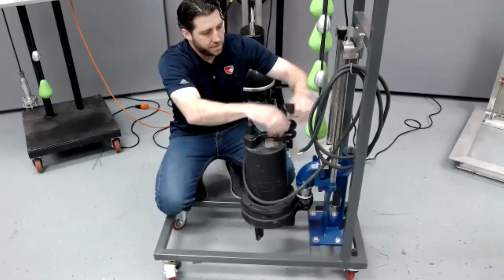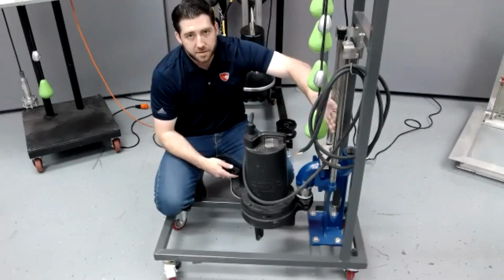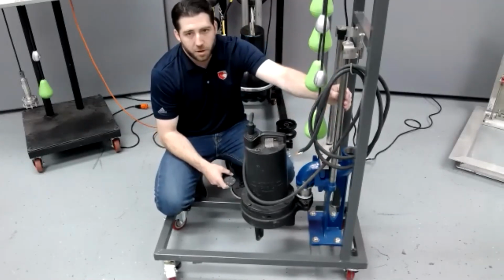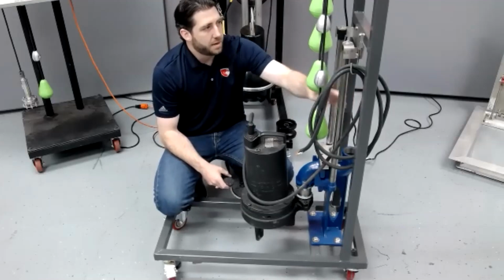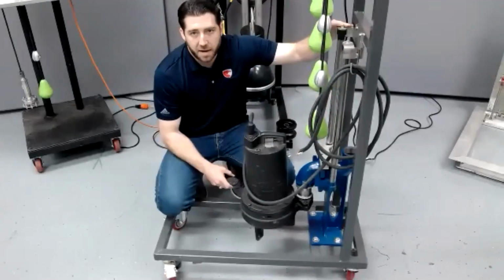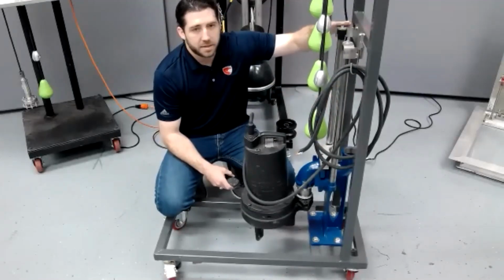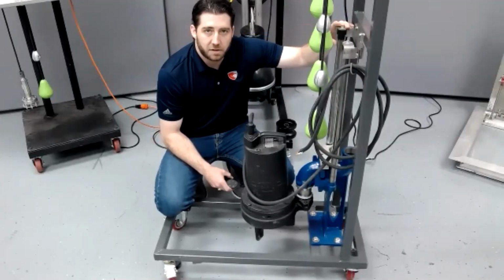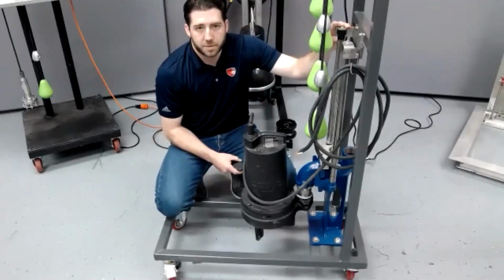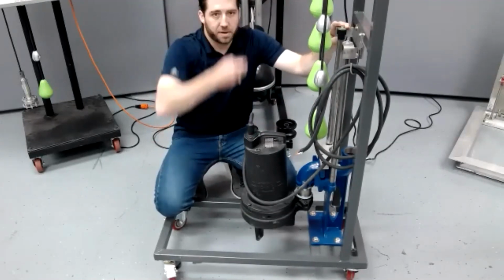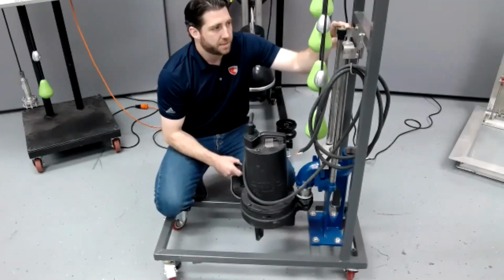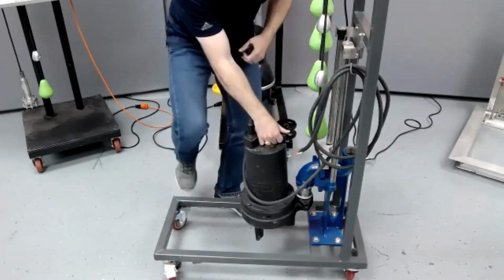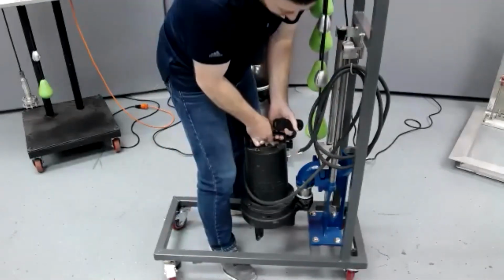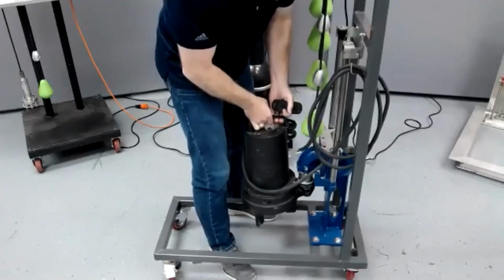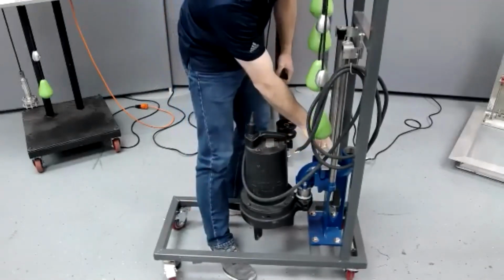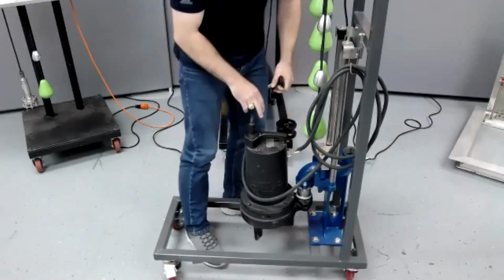So you can see the guide rails here, stainless steel. You always want to go stainless steel on your rail piping so that it doesn't corrode, being in that moist environment. And our upper guide bracket here is always going to be stainless steel as well. This is what would be installed on the underside of the cover, and that would align the pump to be able to pull it straight out of the hatch. Okay, and this one is small enough that I can lift and show you. So you can see it rides up and down right there, and it is going to seal back once it goes down.